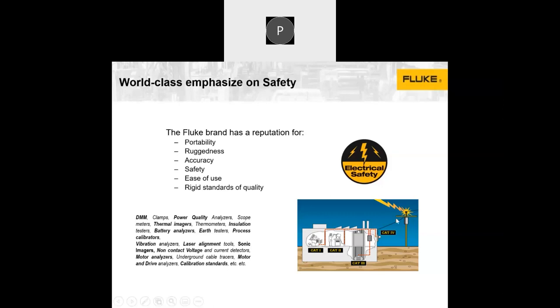Why is it required? The category ratings classify different working areas based on studies. If a high voltage area is present, like a yard or a railway line with a high voltage transmission line, distribution line, or transformer, where expected voltage is 8 kV and above, that falls under category 4. If you use a multimeter designed for category 2, the expected voltage there is only 4 kV.